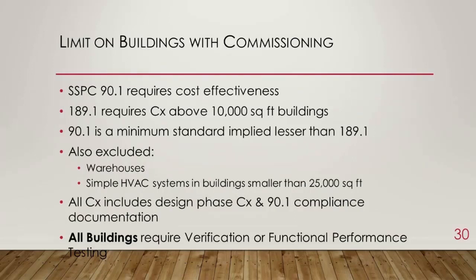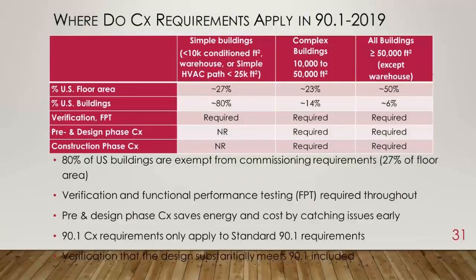So all commissioning does include design phase commissioning. There was some discussion about whether we should cut that off at 50,000 square feet. No, it's cut off at 10,000 square feet, or 25,000 for simple systems. There is a design review required in 90.1, and we do require verification or functional performance testing. And again, we've reviewed earlier where the commissioning is required. We wanted to apply the Pareto principle and capture the more complex buildings where commissioning is of benefit.